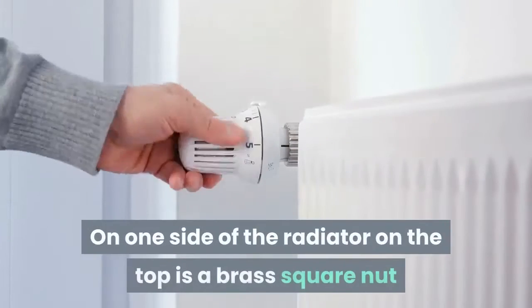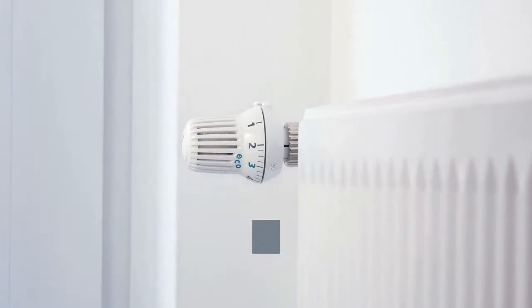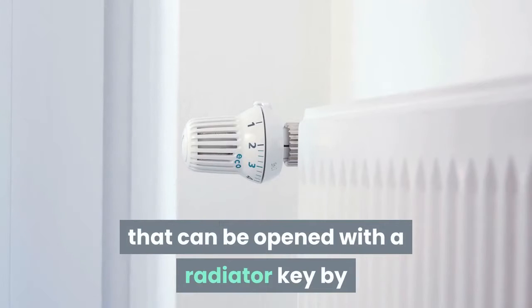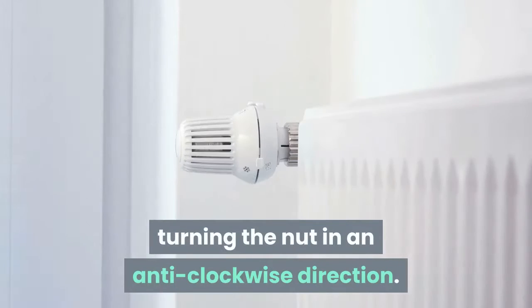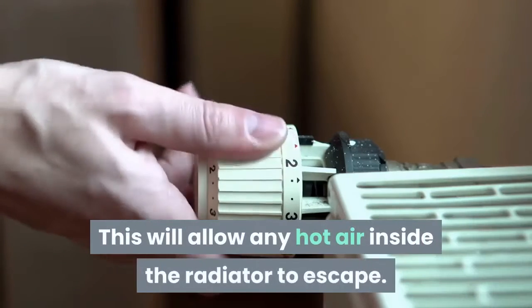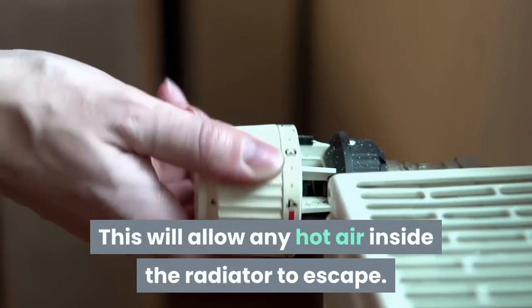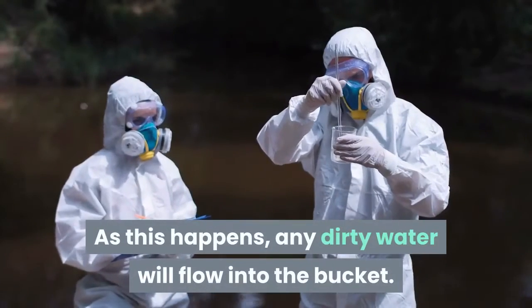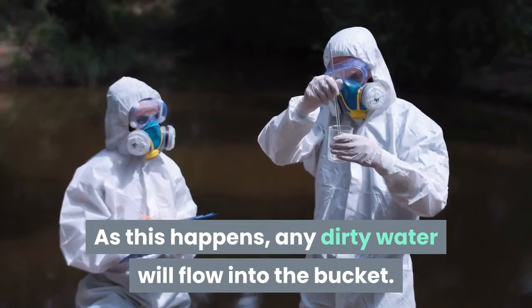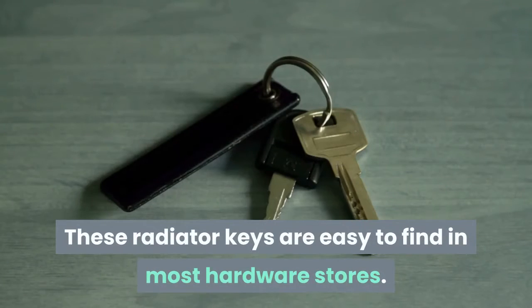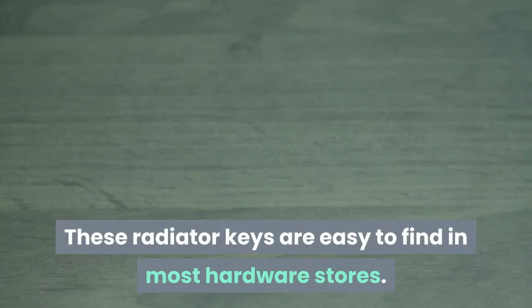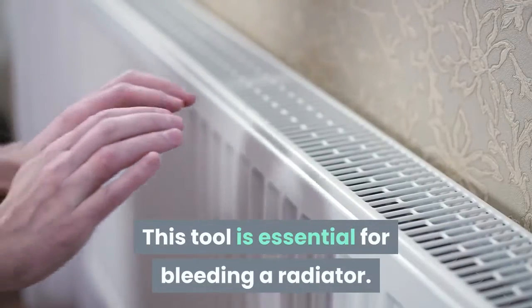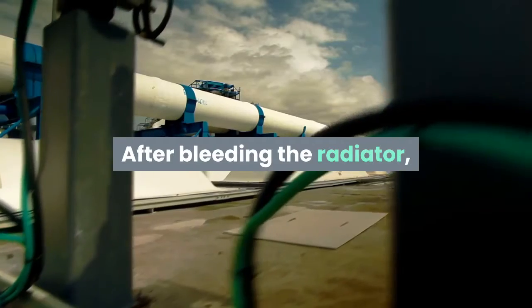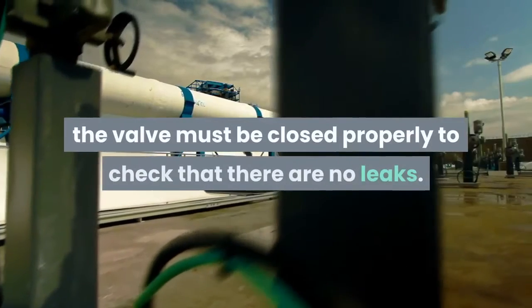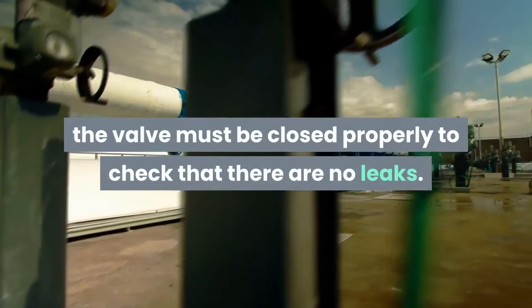On one side of the radiator on the top is a brass square nut that can be opened with a radiator key by turning the nut in an anti-clockwise direction. This will allow any hot air inside the radiator to escape. As this happens, any dirty water will flow into the bucket. These radiator keys are easy to find in most hardware stores. This tool is essential for bleeding a radiator. After bleeding the radiator, the valve must be closed properly to check that there are no leaks.